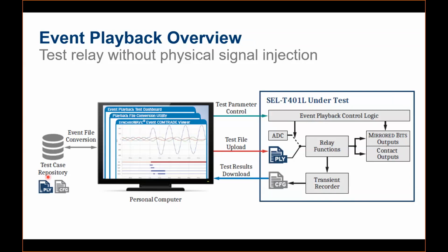It's a very good tool that you don't need a test set to run or play back that event on the computer to inject that relay. We can just load the computer files into the relay, and the relay will be playing them. And you can find the results for the protection functions, how TW behaved for that, how TD21 behaved for that, and how the phasor-based protections behave for that.